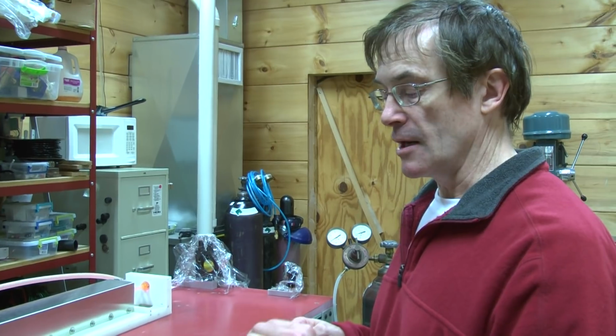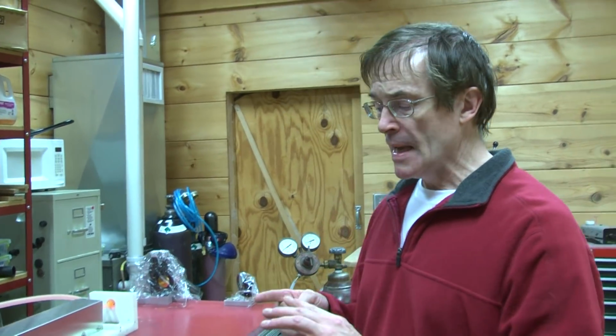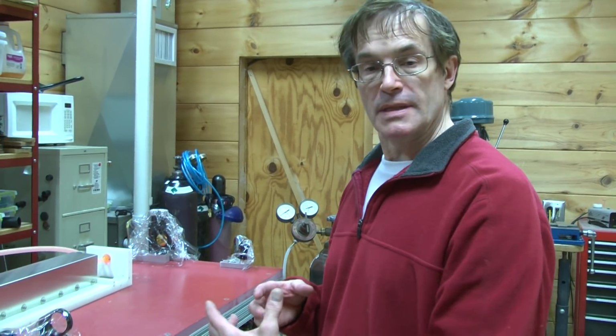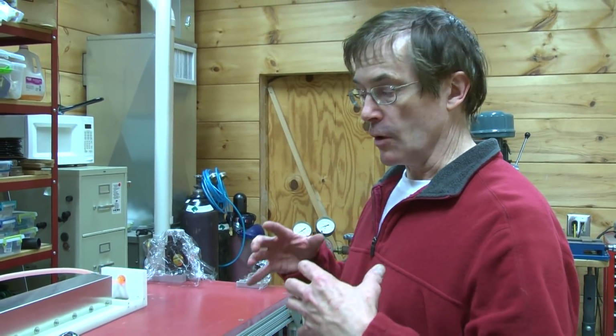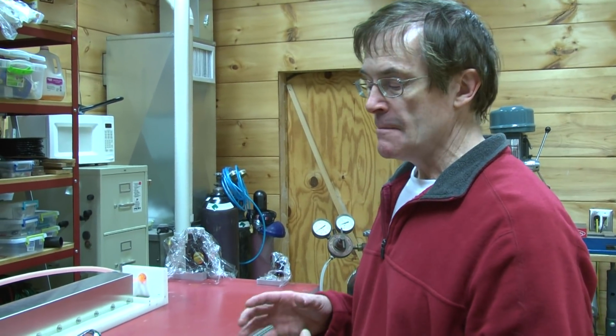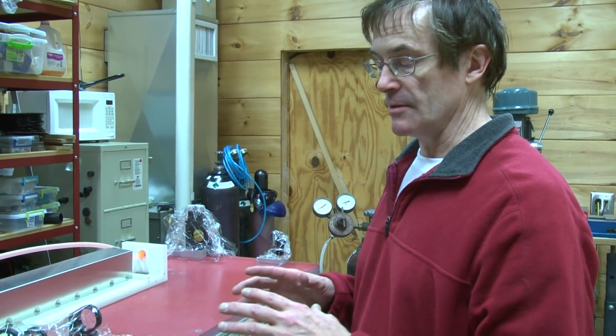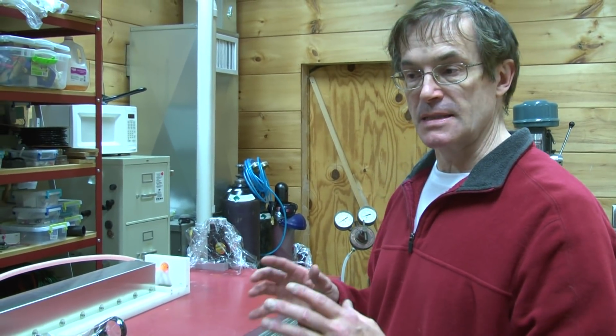Discharge capacitors have a very low self-inductance. The lower the inductance, the faster the capacitor can output its energy. For energy discharge or flash lamps, you don't want capacitors with inherent inductance greater than about 1 microhenry. The very best ones get down to tens of nanohenries, which is important for high speed.